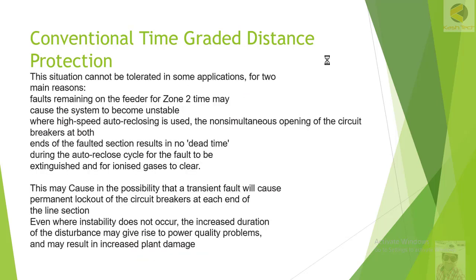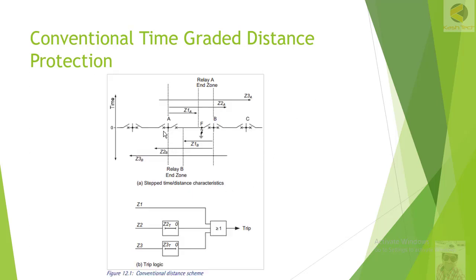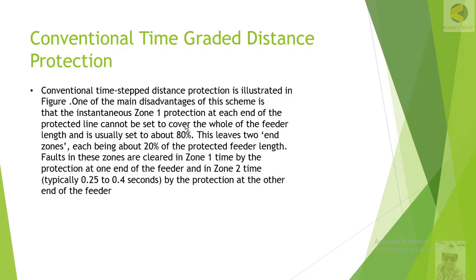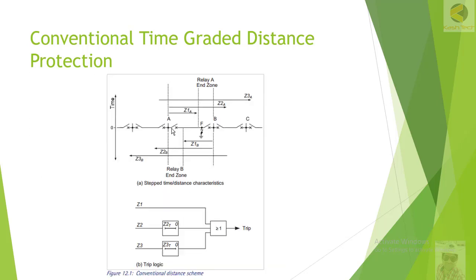Here you can see Zone 1 at Station A. This is the Zone 1 region, which is 80% of the line. The line is between A and B. So if there is a fault between A and B, let's explain why we are not taking Zone 1 as 100% of the line.